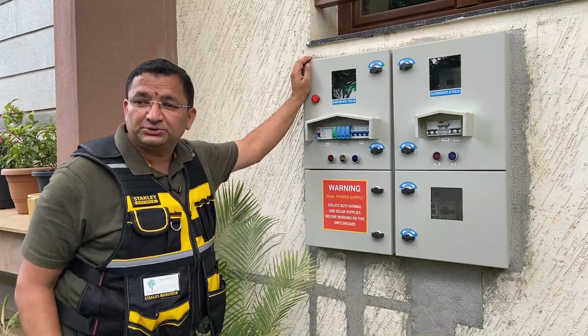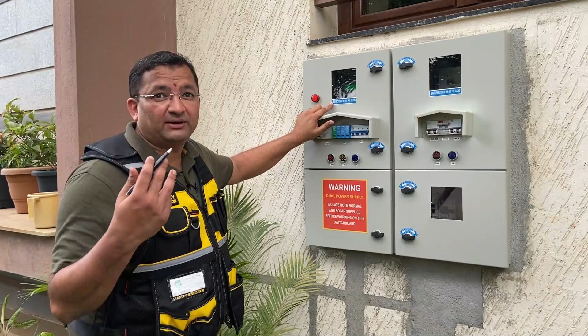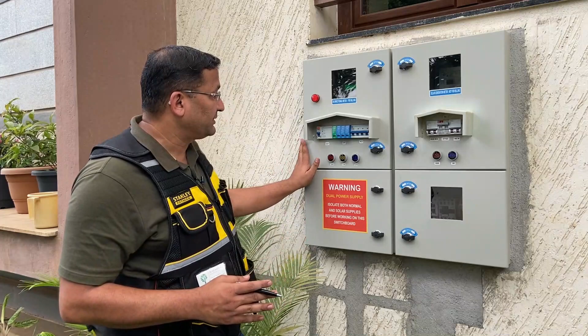So the AC side of the wiring starts from the main distribution panel of the house. The incoming DISCOM power comes into this bus bar, and this is our bidirectional meter. Since this is a grid connected system, this inverter can also export power into the grid. So this bidirectional meter can record both the power taken from the grid and the power given back into the grid.